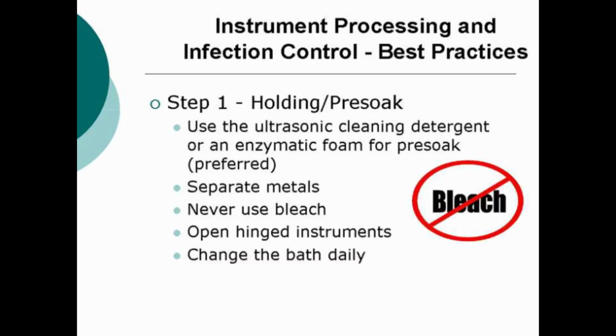You want to use an ultrasonic cleaning detergent or enzymatic foam for pre-soak. You want to always separate metals. This includes carbides from stainless steel. You never want to use bleach. Always open hinged instruments to their full open position, and you want to change the bath daily.